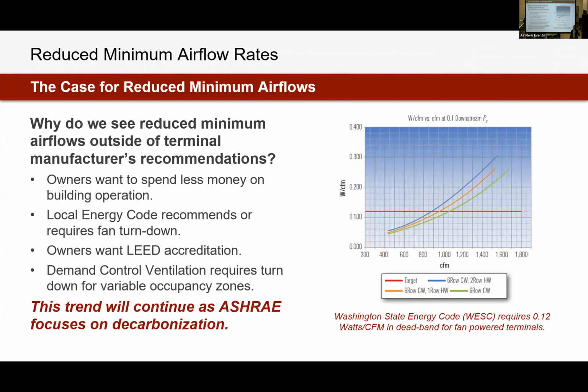So again, why is this a topic right now? We want to save money and be conservative with energy in general, but then also save money on the building operation. LEED accreditation could factor into this, or even state codes. So here's a little note on the Washington State Code. I mentioned Seattle is really strict. Their energy requirement is 0.12 watts per CFM in deadband. So for fan powered boxes, we're having to turn down fans really, really low to make sure we're meeting that code.